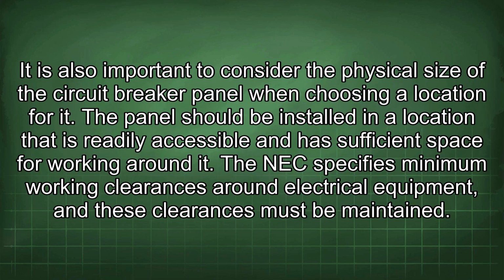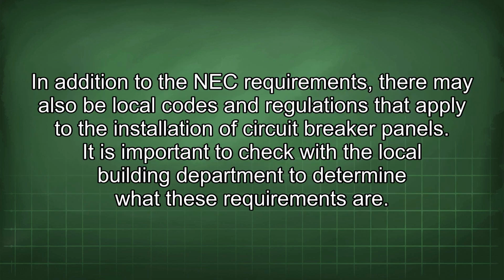It is also important to consider the physical size of the circuit breaker panel when choosing a location for it. The panel should be installed in a location that is readily accessible and has sufficient space for working around it. The NEC specifies minimum working clearances around electrical equipment, and these clearances must be maintained. In addition to the NEC requirements, there may also be local codes and regulations that apply to the installation of circuit breaker panels. It is important to check with the local building department to determine what these requirements are.